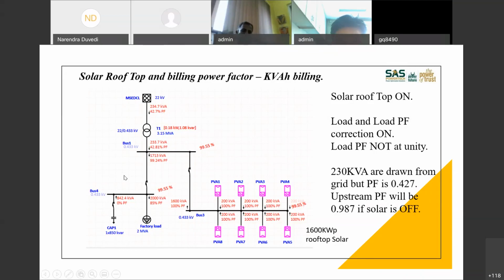So these are the basic combinations showing the effects of having a rooftop solar on your billing power factor. You have to take care that at all times your load power factor is compensated to whatever is required. Again, it has to be real time, because your solar power on your holidays is going to change from 7 o'clock in the morning till 4 o'clock in the evening. It's a bell curve. So you may not get 1600 kilowatts continuously. You may get less in the beginning, more in the afternoon, and again less in the evening.